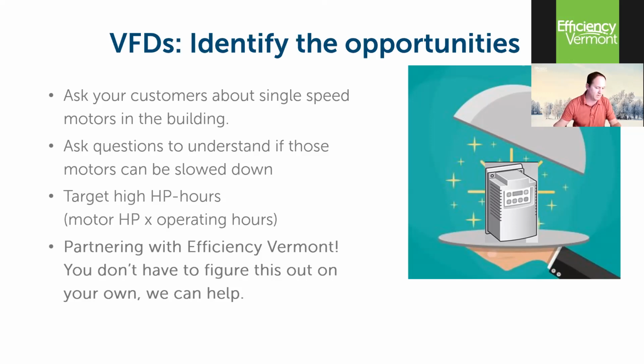And then another question, a corollary to that: do you have any motors, pumps or fans in your building that you think could be slowed down? And we get all kinds of answers. We get, there's no snow on that side of the building because we exhaust so much heat over there. Or, it's really cold in the kitchen during the week at a ski area because we're exhausting so much heat out of there. Or, it's really cold in the conference room because there's so much airflow in there. Those are some key indicators that you're overdriving a pump or a fan, and there's an opportunity there to slow it down via a VFD.